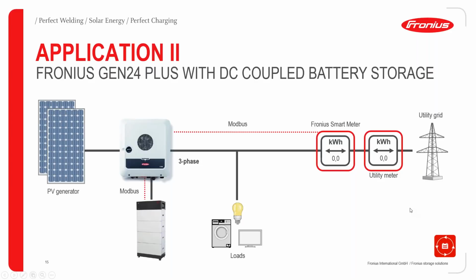If you then add a battery, application 2 would be a DC-coupled battery storage. That's the Fronius storage solution, a DC-coupled high voltage battery storage directly connected to the inverter. We communicate again via Modbus, and with BYD you need an additional plus 12 volt signal. I'll come to that later.